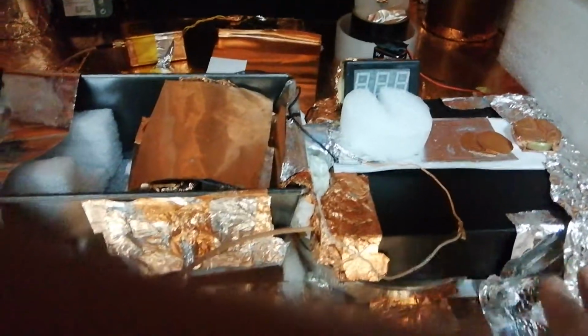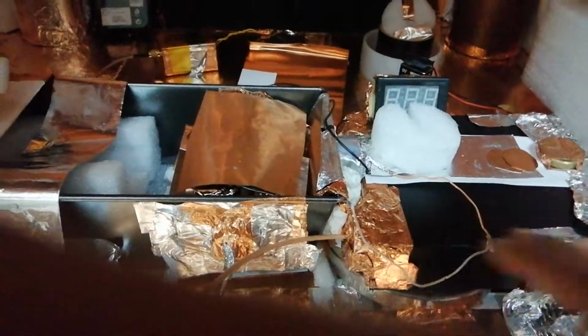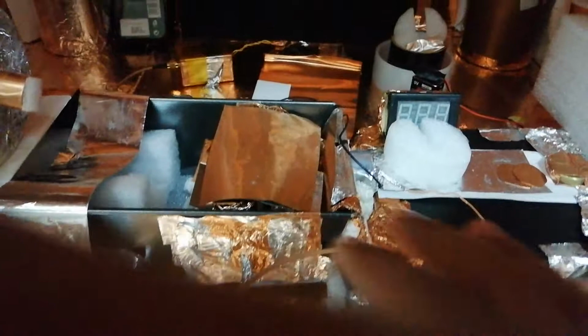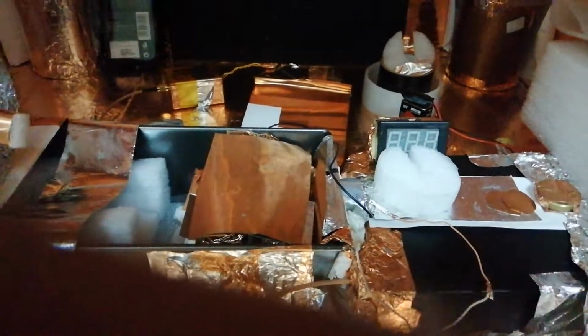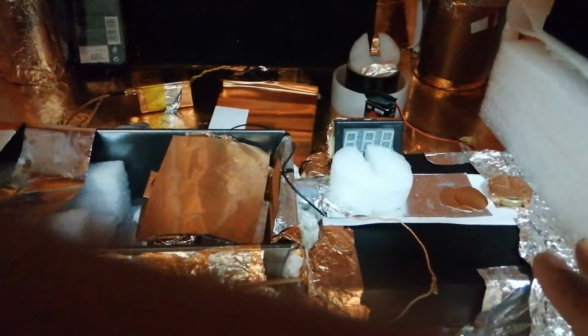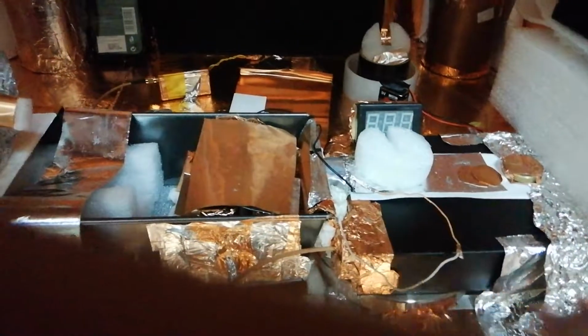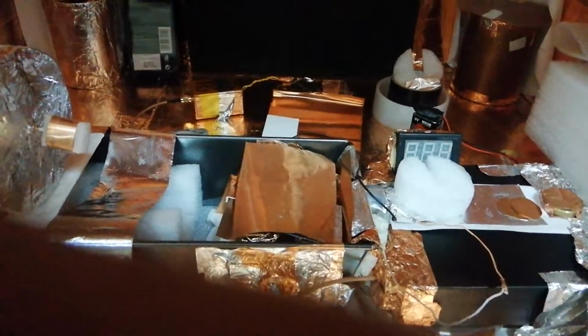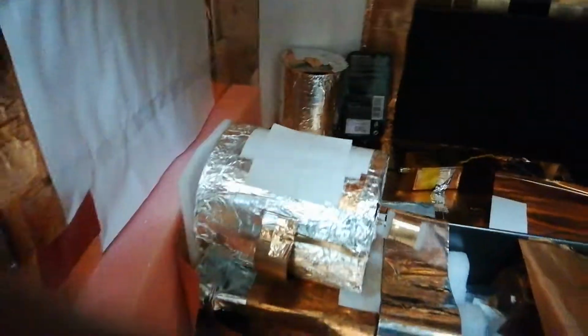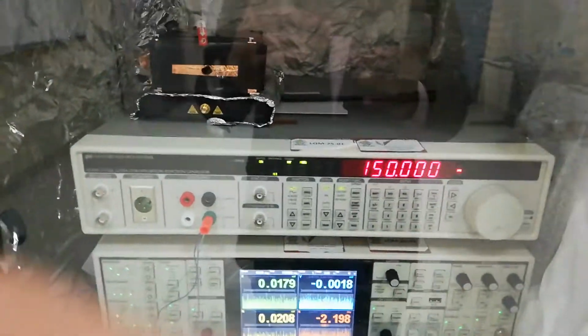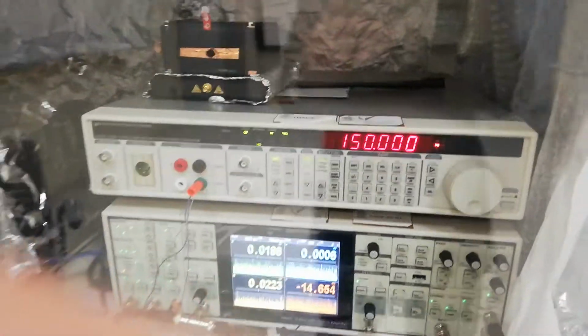What you see here, this black box, which is literally a black box, is the workhorse for this measurement, which has the tunnel detector, the SQUID assembly, and then an RF detector. So all this then tries to generate a signal, and you have a bias circuitry that provides a very, very high precision voltage bias, which is required to maintain these. And then you have the signal coming in from a very ultra low distortion signal generator, which generates the synchronization signal for this.